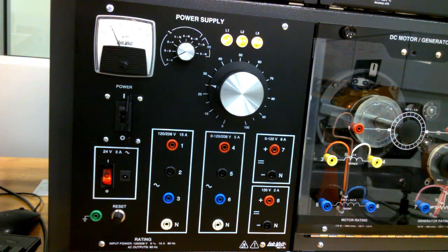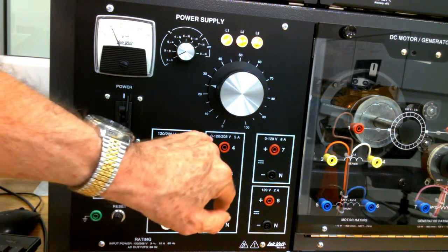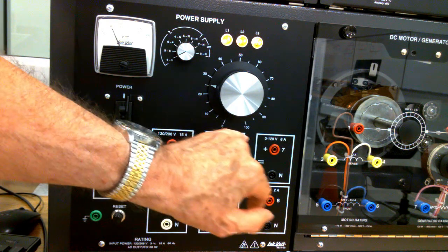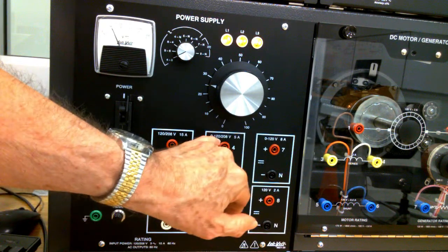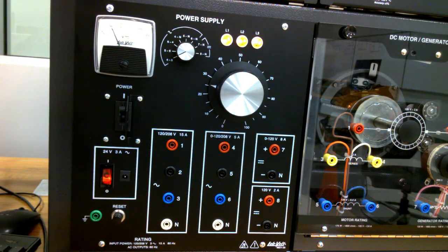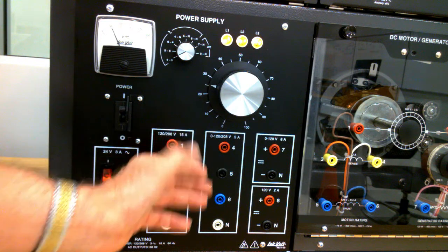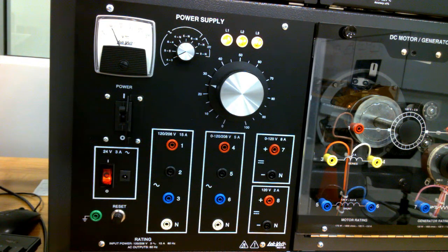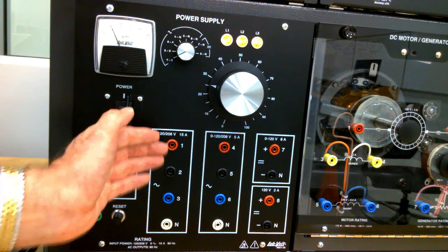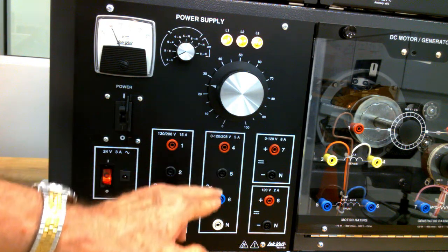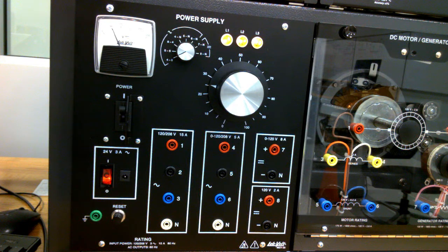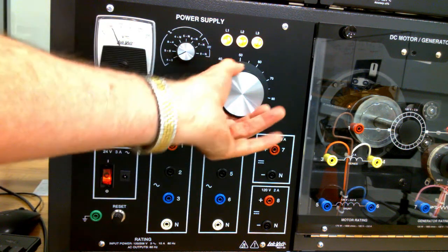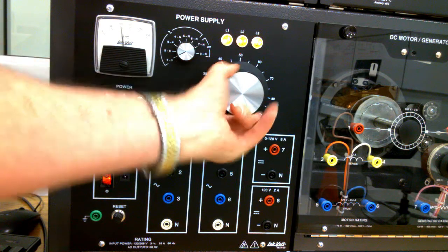Now then, we have something that looks the same over here, but if you notice, this one is variable. It will vary from 0 volts up to 120 or 208, depending upon what your choice is. The red, black, and blue terminals work the same way that these do, except the voltage is variable. Now then, how do we get a variable voltage? Well, we use this thing right here. This is called a variac. It is a variable transformer.